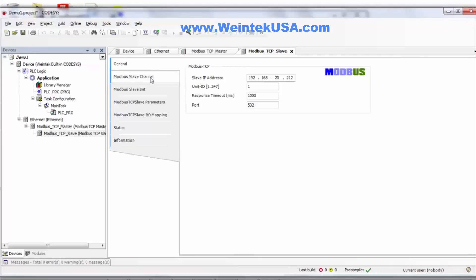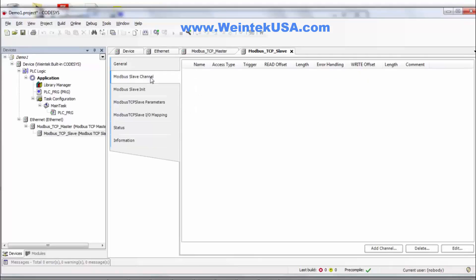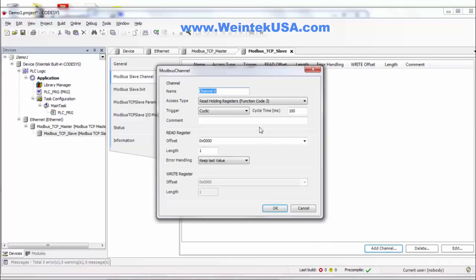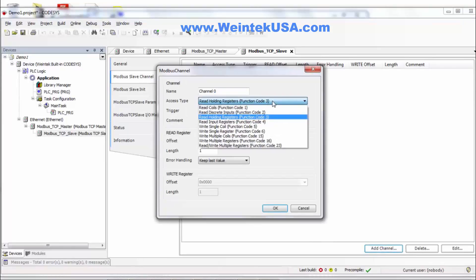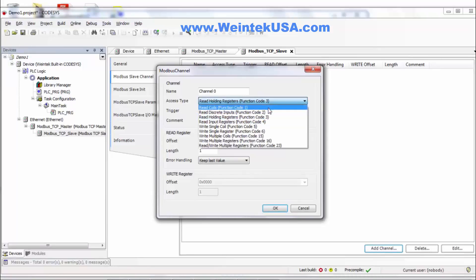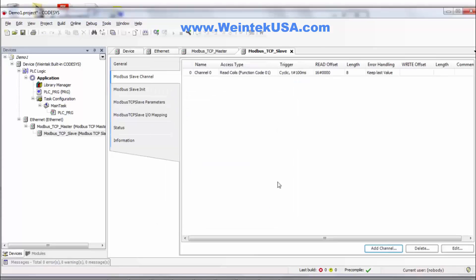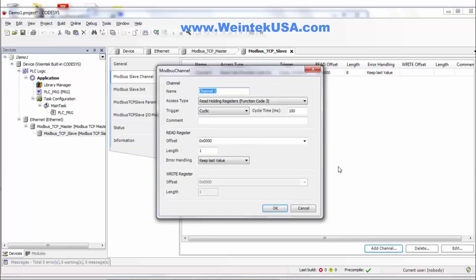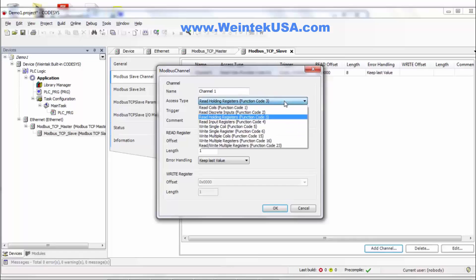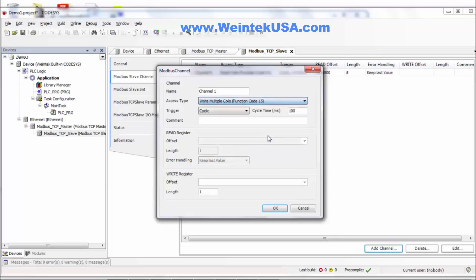Now we need to go ahead and set up our slave channels. So we need to go ahead and click add channel. We want to read coils, function code 1. We're going to do an offset of 0 because this is our first device. And we've got 8 inputs. We need to add another channel which is going to be write multiple coils, function code 15, offset of 0, and a length of 8.